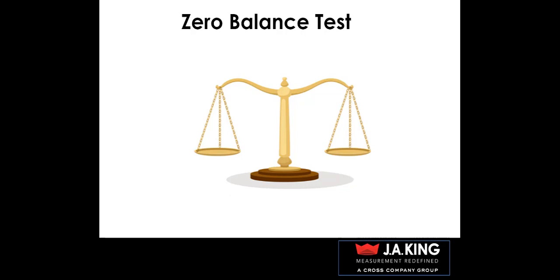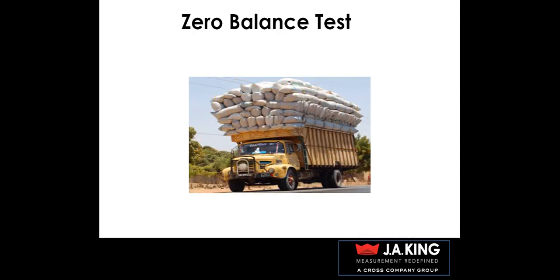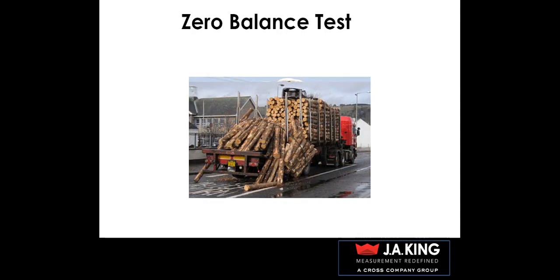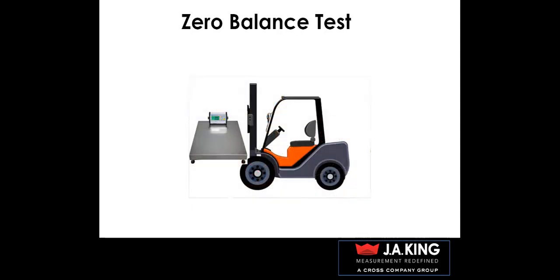A zero balance test can help determine if the load cell has been subjected to any physical damage such as an overload, shock load, metal wear, or fatigue. And you must make sure the load cell is in a no-load condition before starting. This may require using a forklift to lift the scale or a jack to take pressure off of the cell.